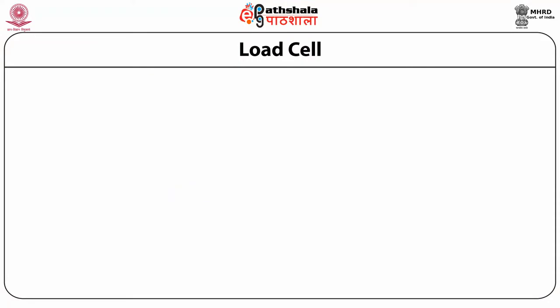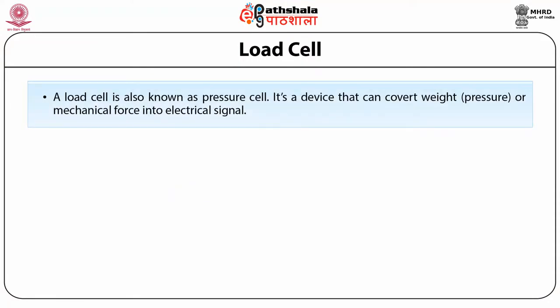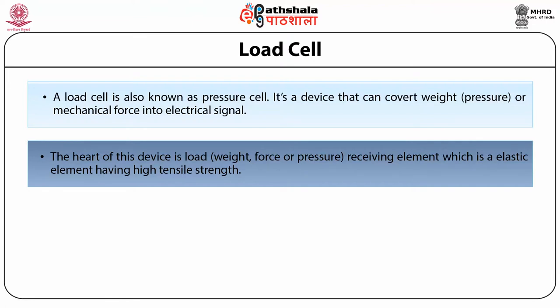Load cell. A load cell is also known as a pressure cell. It is a device that can convert weight, i.e. pressure or mechanical force, into electrical signal. It is widely used for measuring dynamic and static forces. The heart of this device is a load, i.e. weight, force or pressure receiving element, which is an elastic element having a high tensile strength. This element is bonded to a strain gauge bridge network.